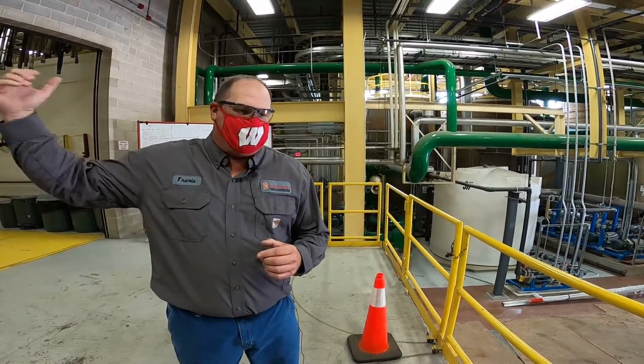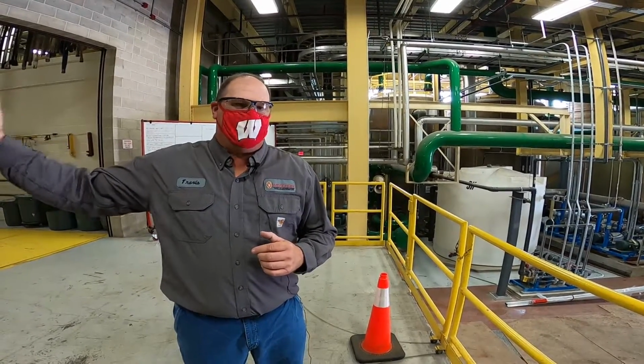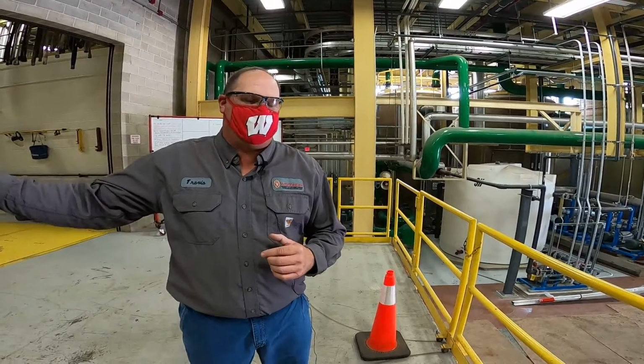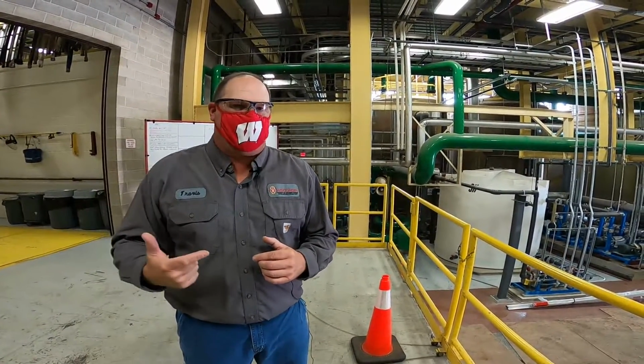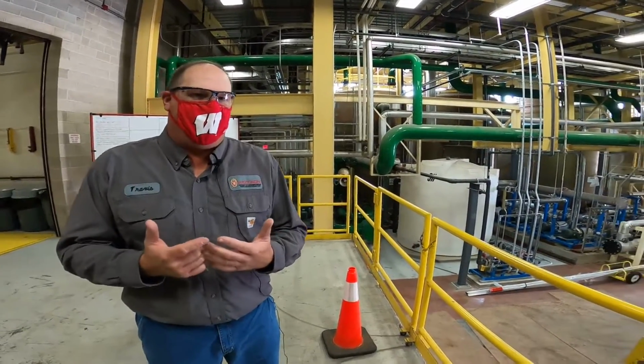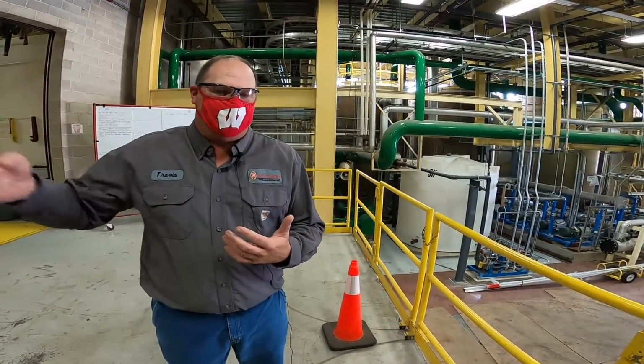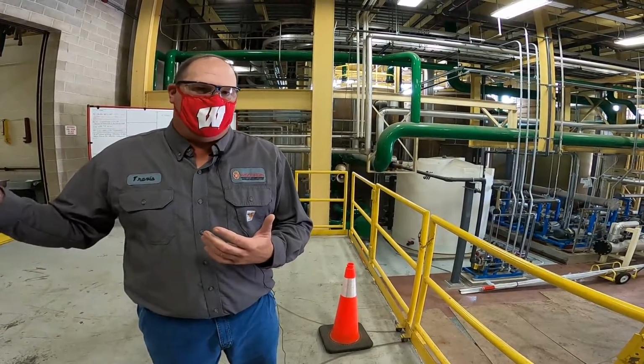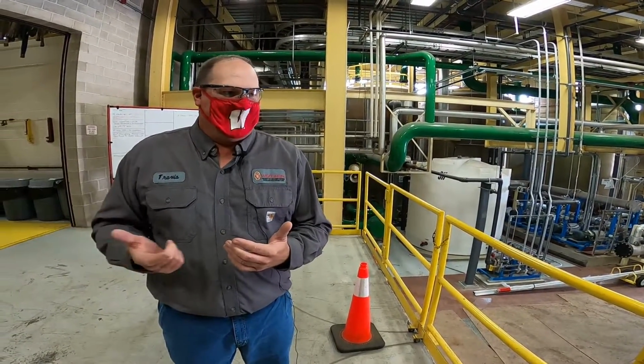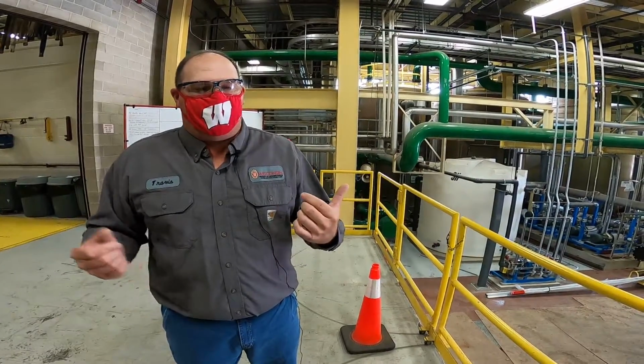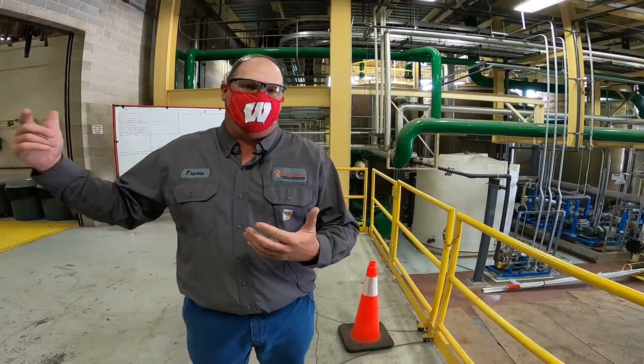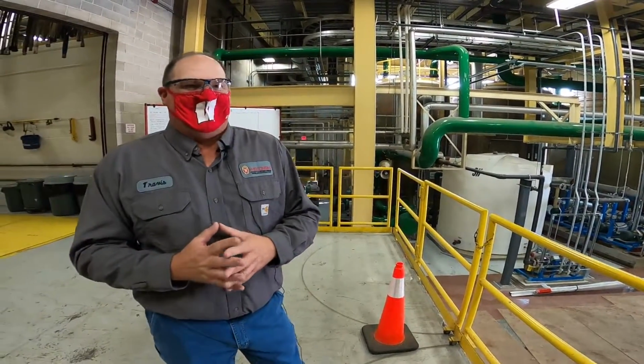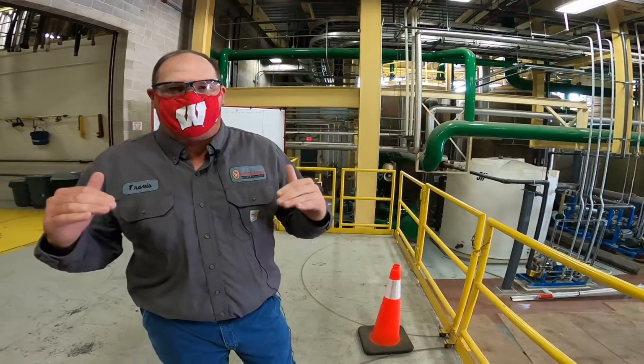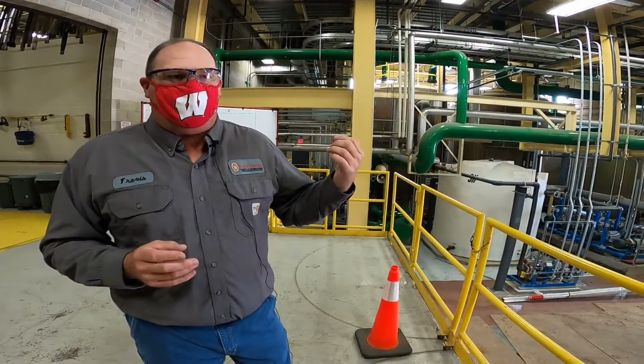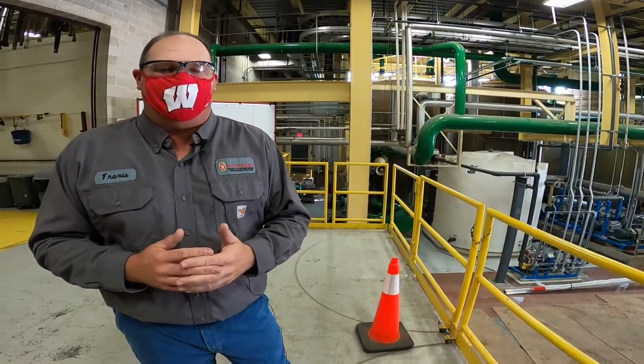So the condensate, the steam that goes out to campus, when it goes through that air handling unit, it condenses into condensate, and that condensate needs to come back to the plant. We reuse that water and boil it, make steam, and it's a continuous cycle. If we don't get at least 80% of that back, there's potential we could run out of water and we'll have to shut down a section of the steam system because we wouldn't be able to sustain the boiler steam capacity to campus. We watch that closely and the levels of our tanks, and we have some people that are employed to maintain that system 24/7 here at the plant.